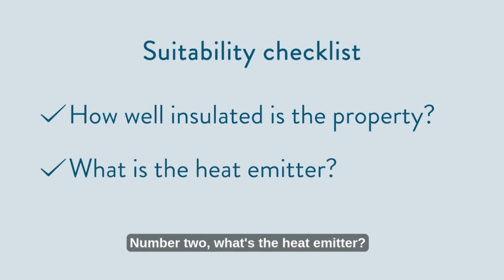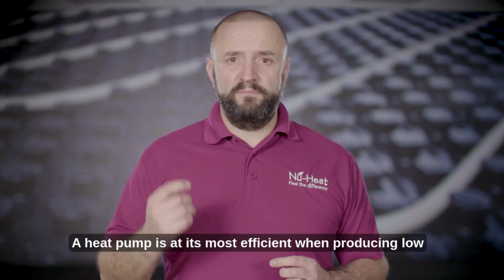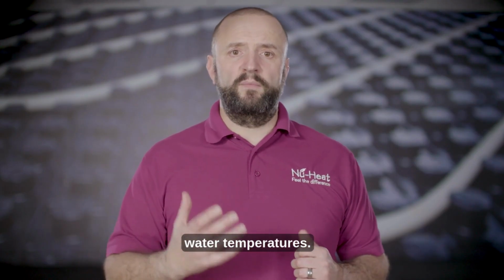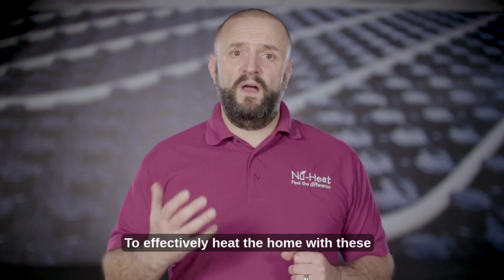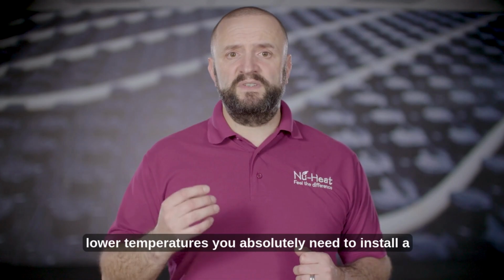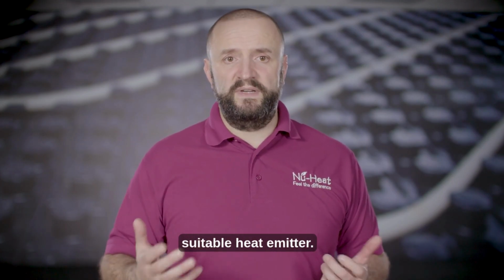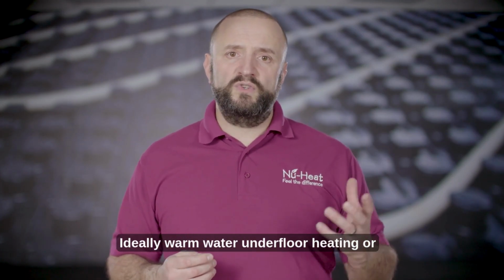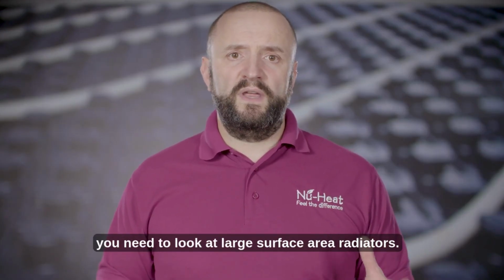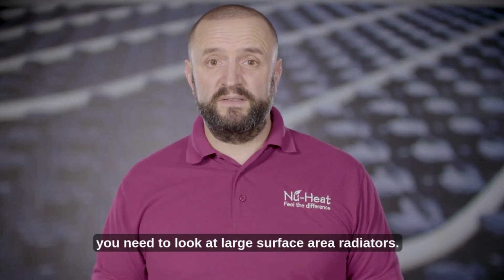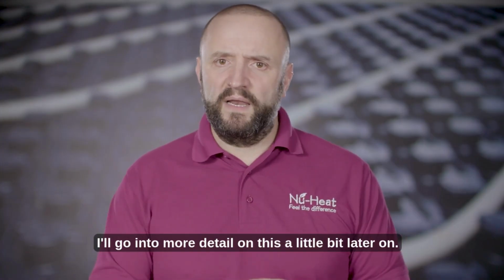Number 2, what's the heat emitter? A heat pump is at its most efficient when producing low water temperatures. To effectively heat the home with these lower temperatures, you absolutely need to install a suitable heat emitter. Ideally, warm water underfloor heating, or you need to look at large surface area radiators. I'll go into more detail on this a little bit later on.